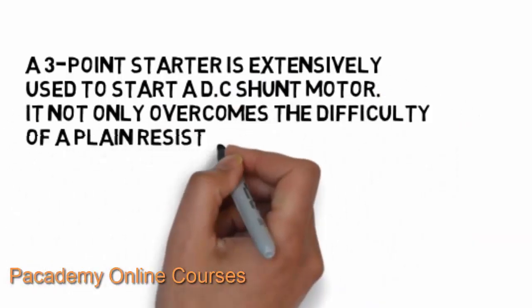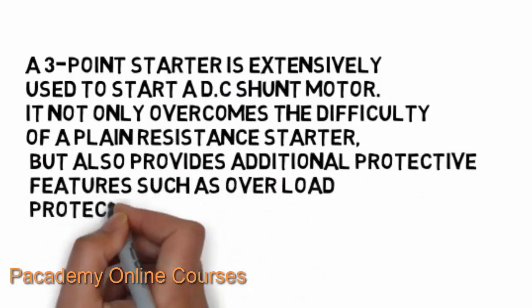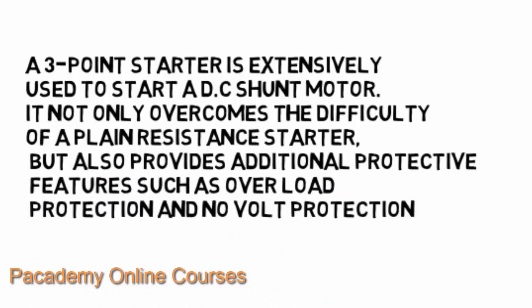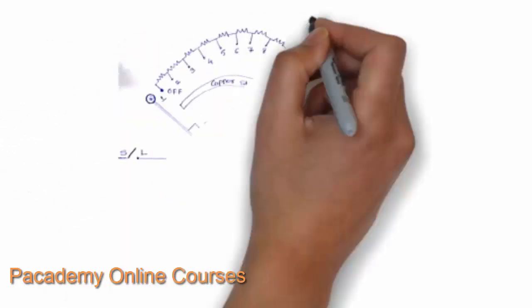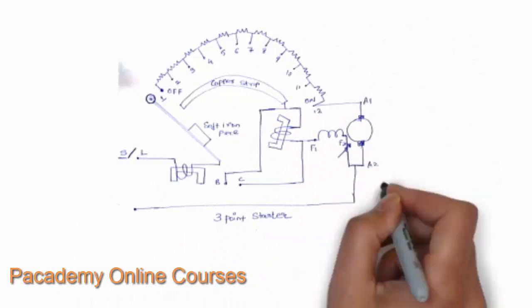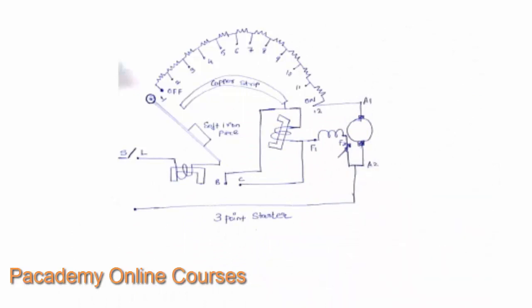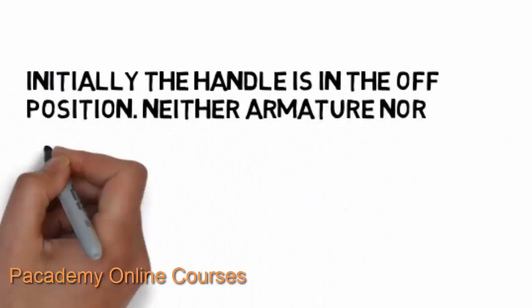This disadvantage can be overcome by a three-point starter, which is extensively used to start DC motors. It not only overcomes the difficulty of a plain resistance starter but also provides additional protective features such as overload protection and no-volt protection — that is, protection when the voltage is removed. In this type of starter, when the supply is disconnected, the starting resistance is also automatically reset, and to start the motor again the starting procedure must be repeated.